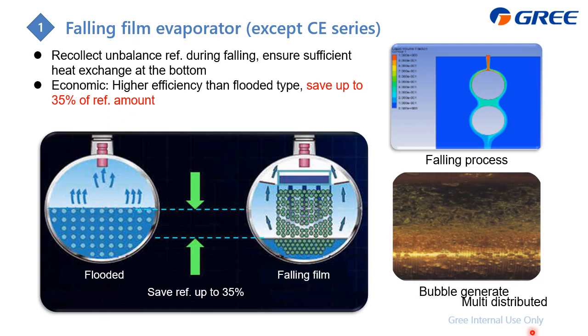And what's the problem with it is, from this picture, you can find it on the surface of the tube. There, the liquid refrigerant is boiling, and the boiling will always generate bubbles, right? The bubbles always mean the heat transfer resistance will be higher, and this will lower the heat transfer efficiency. And for the falling film, we will collect the liquid refrigerant and spread it on the surface of the tubes, and the tube inside is also the water. Also it can cool it down, but just like this, you can also find it when we spray on the tube, and then the refrigerant absorbs heat and then flows out, which means there will be fewer bubbles, and fewer bubbles mean less heat transfer resistance.